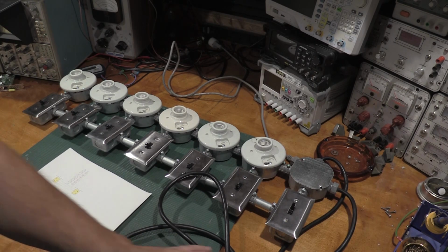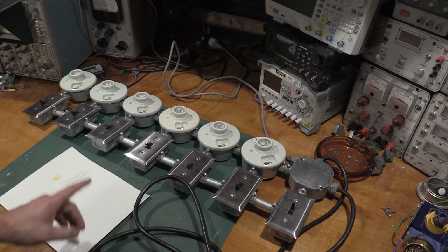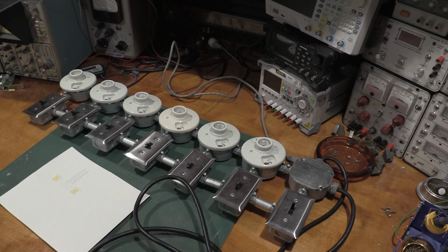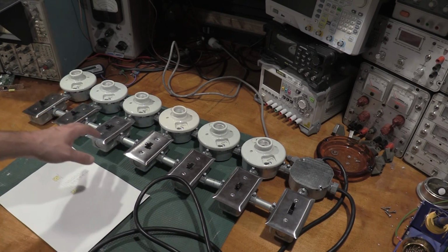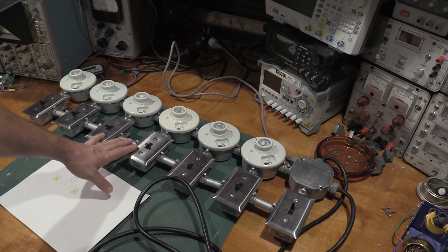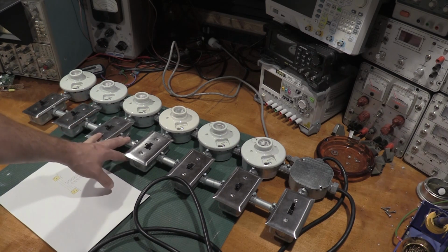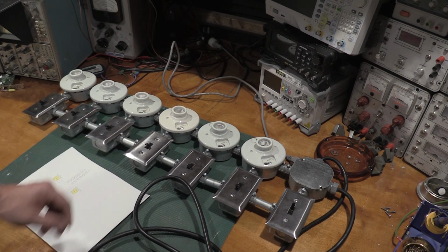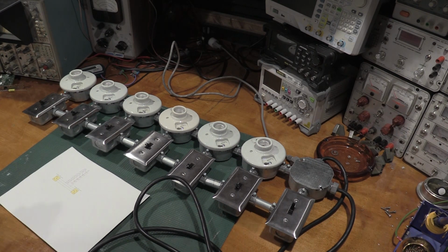So this is fine for the dim bulb tester. Also, the Variac tops out at 2000 VA. So the weak link in all of this is actually the isolation transformer itself, because the isolation transformer is only good for 1000 VA. This is completely fine as built. This will take anything the isolation transformer will, and I'm just careful not to burn down that isolation transformer because that is not cheap to replace.